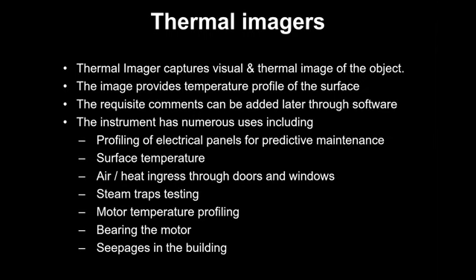Heat or air ingress also can be checked. You take an image of a door. Now if it is a cold storage, if you take the door image, you will know if through the gap something is going in, again that will be at a higher temperature. So that will tell you. Even normal windows, like HVAC, office windows also, we have done thermography to find out the leakages, ingress points and all that. Steam trap testing, I told you already. Motor temperature profile, I think Ashok had already mentioned. Bearing temperatures, even seepage into buildings can be measured, because there are thermal imagers available with 0.1 degree difference. So you can do that measurement. And specifically, there are thermal imagers available for building audit. We don't have that, but it is available.